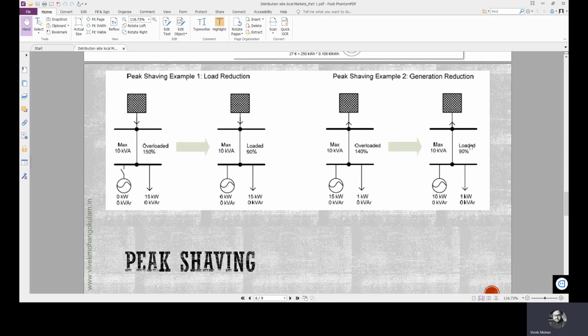Now in the second case, the generation has come down to 10 kilowatts, then load is still 1 kilowatt. So now the excess generation is 10 minus 1, which is 9 kilowatts. So 9 kilowatts is pumped to the upstream grid, and that's why this line is now 90% loaded.